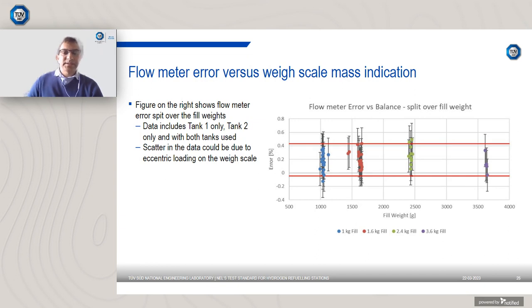The data points that you can see here are for the flow meter error versus the mass scale indication from the gravimetric system. And it contains data for the different tank configurations. So if you use just one tank, or if you use two tanks, or for example, if you use a smaller tank versus a larger tank as well. And as a result of this, because the tanks are installed side by side, you could get some eccentric loading on the weigh scale, and some of the scatter in the data could be due to that.